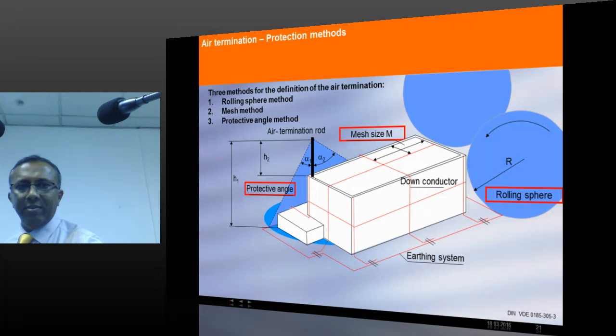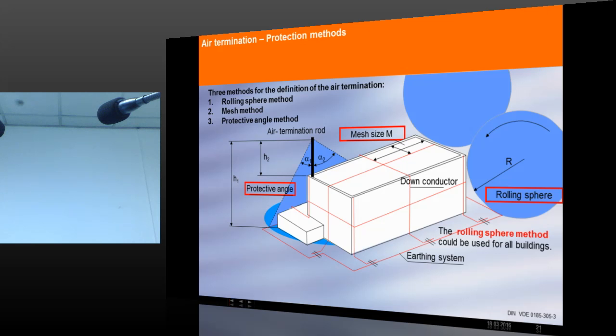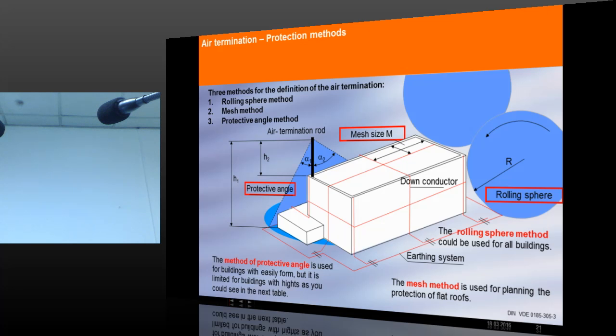So now, air termination. There are three methods explained in the standard. One is a rod, which offers a certain angle of protection. I don't know about the older standards, whereas in some places, for example India, the old standard says the protection angle is always 45 degrees. But now, what is explained in the standards? Here you can see alpha 1 and alpha 2, the protection angle at one side of the rod and the other side of the rod. Alpha 1, the protection angle, is less at one point of the building because the height of the place to be protected is more. So the angle of protection depends upon the height of the building as well as on class 1, class 2, class 3, class 4, whether you need 200 kA, 150 kA or 100 kA protection.